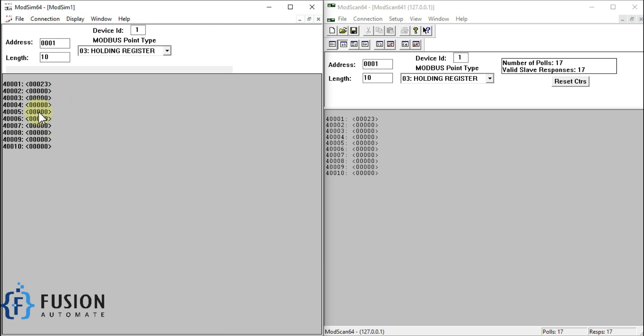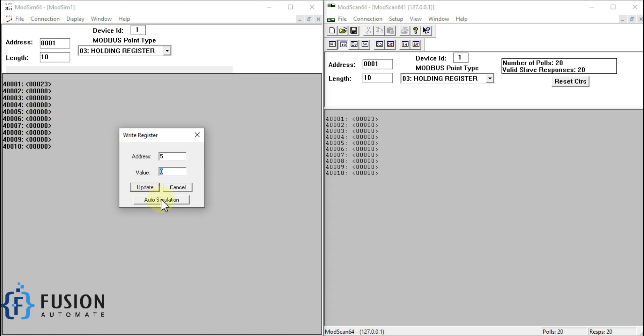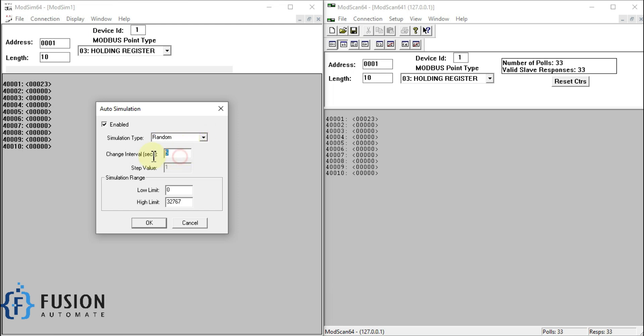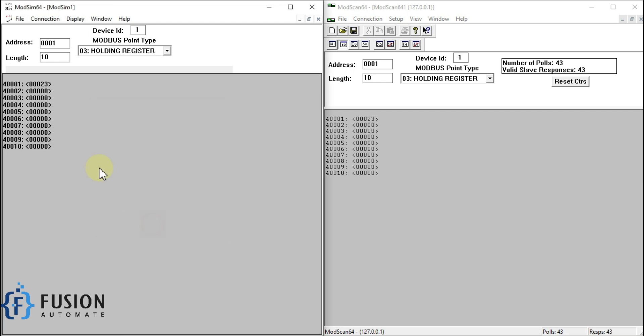Now I want to simulate my Modbus TCP server. If I want to simulate the 40005 holding register, I'll double-click on it and press Auto Simulation, then enable it. You can choose the type of simulation — random, increment, or decrement. I will choose random here, with a change interval of two seconds. The low limit is 0 and the high limit is 32767. Once you press OK it will change the value of the 40005 holding register every two seconds.